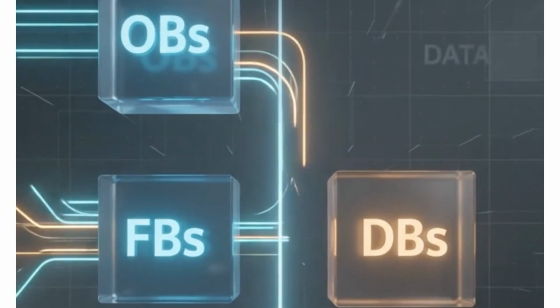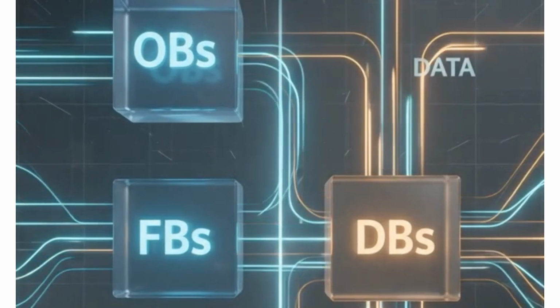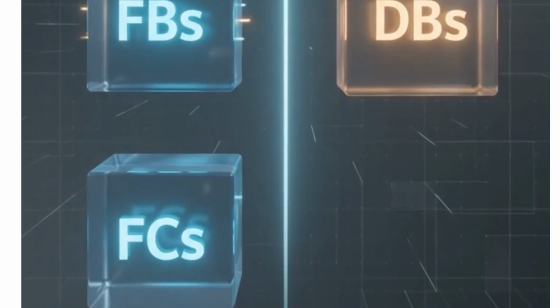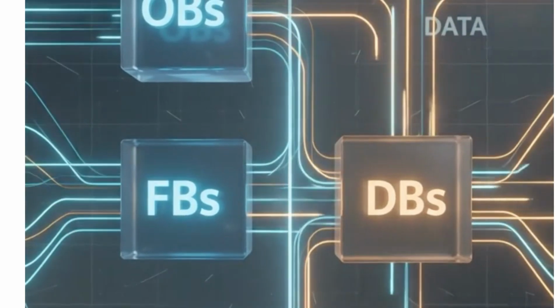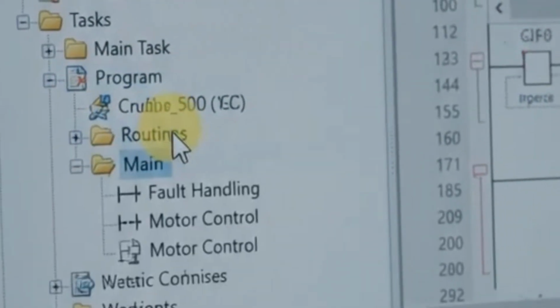Function blocks, FBs, hold reusable logic with their own memory. Functions, FCs, are reusable logic without dedicated memory. Data blocks, DBs, store data separately from the logic itself. It's a more formalized separation between logic and data than Allen Bradley's routine structure, which mixes tags and logic more freely within a program.